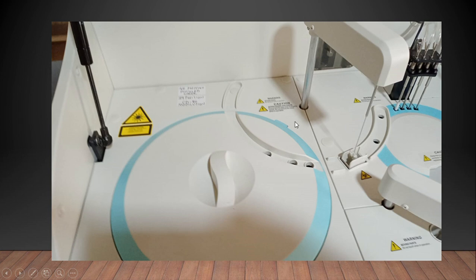So you have to be very careful about when you open this cap and when you replace it back. This problem doesn't appear with the mixer probe, because the mixer probe never comes to the reagent disc at all. This is one area you should always remember. The second thing is, this cap is not very robust, so you have to be very careful. Always look at this particular edge. It has to be kept properly, and make sure that this circle is complete. This half circle which is present should always be complete, so that you know your cap is sitting properly.